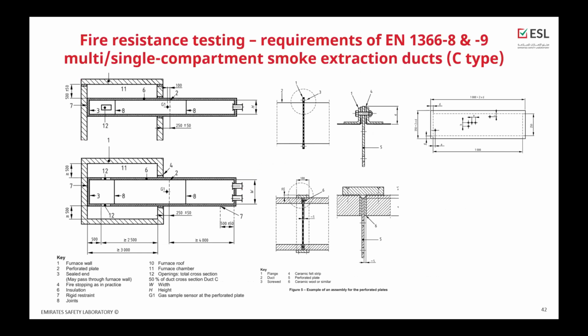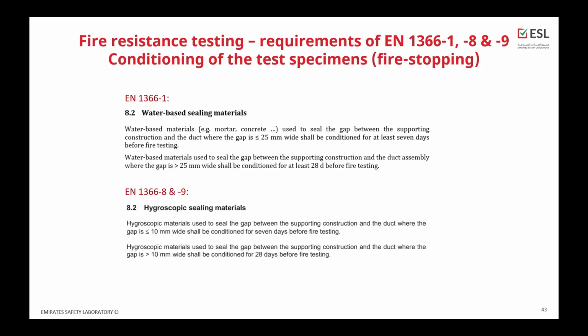The standard is also providing some examples of how we can assemble the perforated plate within your duct, depending on whether this is a steel or a board type system. The standard is also putting some focus on the conditioning of the fire stopping, because if you are using either water-based sealing material or hygroscopic sealing material, and the gap exceeds a certain limit, either 25 or 10 millimeters, you need to be aware that this will affect your plan for testing, because the curing time requested by the standard may be even 28 days.